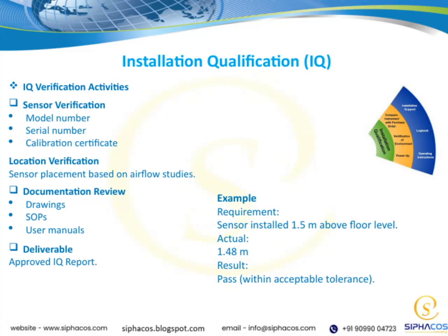Let's walk through an example of installation qualification, or IQ. The requirement here is that the sensor must be installed 1.5 meters above the floor. The actual measurement is 1.48 meters, close enough to pass, since it's within the acceptable tolerance. IQ verification involves several activities: checking the sensor's model and serial numbers, confirming calibration certificates, verifying the sensor's location based on airflow studies, and reviewing all relevant documentation like drawings, SOPs, and user manuals. The final step is delivering an approved IQ report.